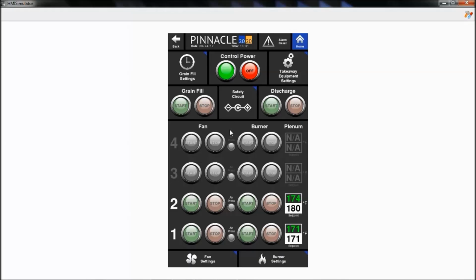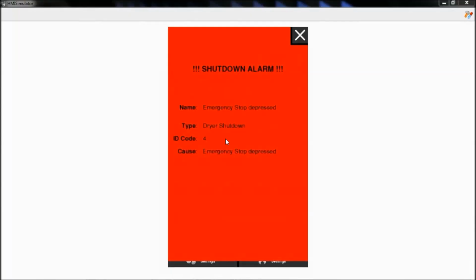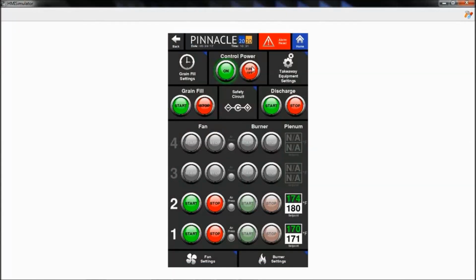So let's imagine that our dryer was on and we had our fan running and our discharge running. Somebody on site sees something they don't like and they push in an e-stop. So an emergency stop is going to cause a critical shutdown alarm. If we hit one now, we see we get a red alarm screen, which indicates a critical shutdown.